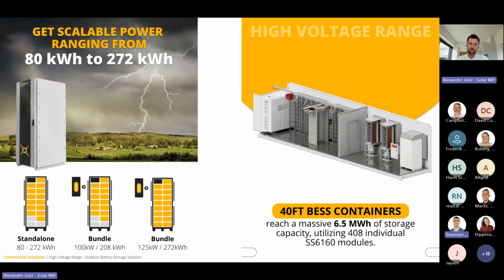Sorry, can I just add to that, to answer the question: it's essentially a voltage compensation to create a linear voltage curve during charge and discharge, and the compensation was maybe a little higher than it should have been. It has been corrected since version 200-plus on the BMS firmware, and it's a lot less aggressive. But if you still have cases where it's overcompensating that voltage, just let us know and we can take it up with the devs. It's most certainly been rectified. I have seen it on version 2, it still does it, but it definitely seems to be less aggressive.